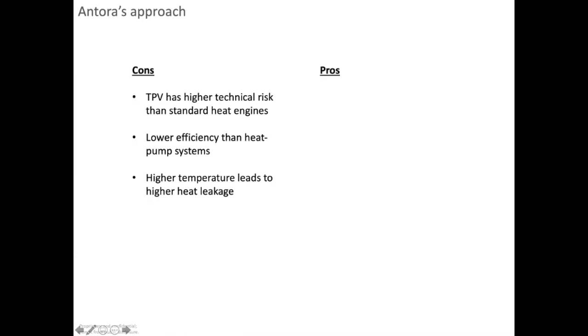And then also, by storing the heat at a higher temperature, you do have more heat leakage. You can solve that by adding more insulation, but you're always going to have a little bit harder challenge there. We typically design for about 1% per day heat leakage, so if you store for a week, you're maybe losing 5% or a little bit more of your power.